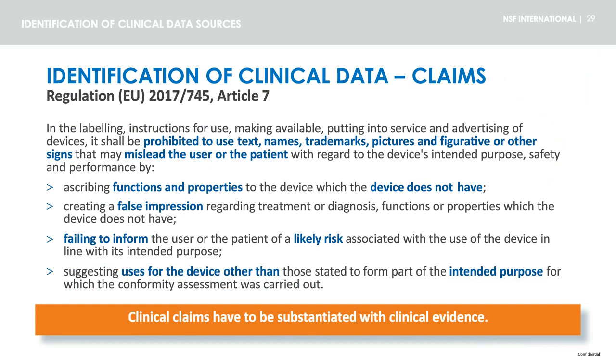Regarding claims, it is important to highlight that Article 7 of the regulation explicitly says that it is prohibited to use text, names, trademarks, pictures, and figurative or other signs that may mislead the user or the patient with regard to the device's intended purpose, safety, and performance.